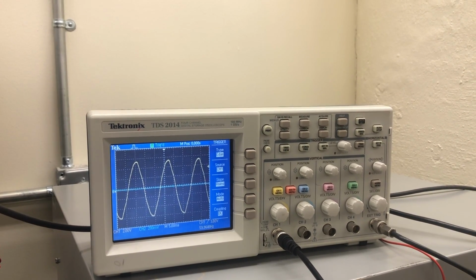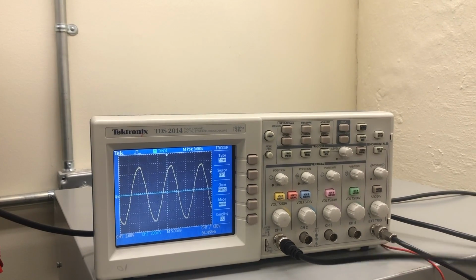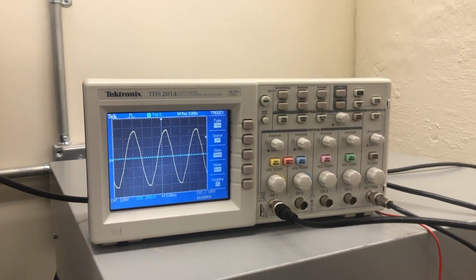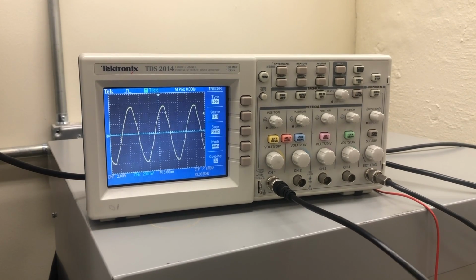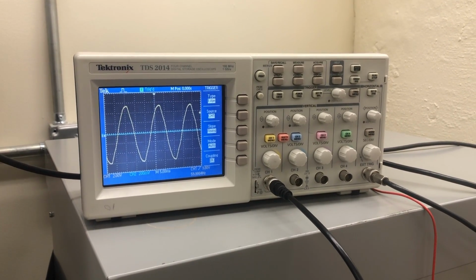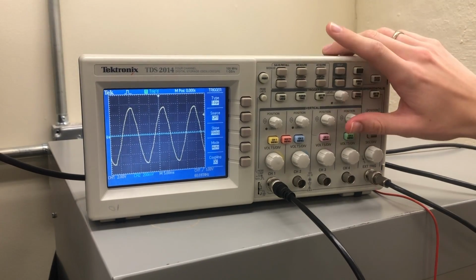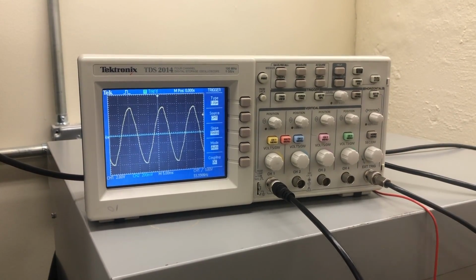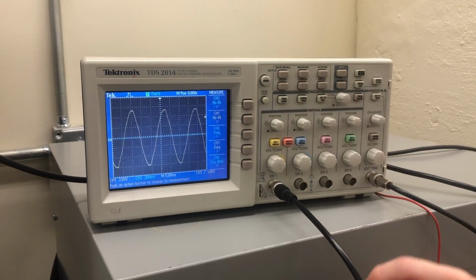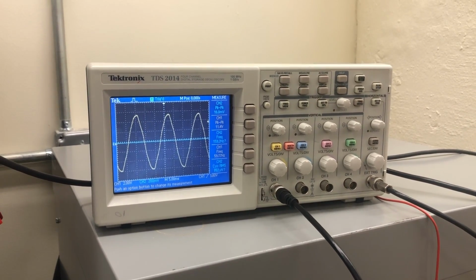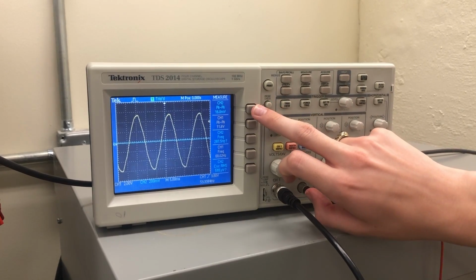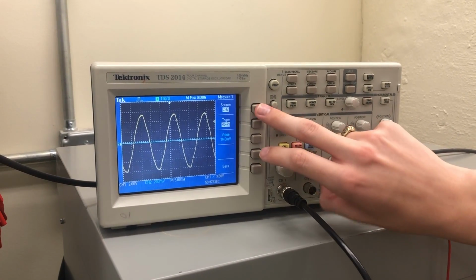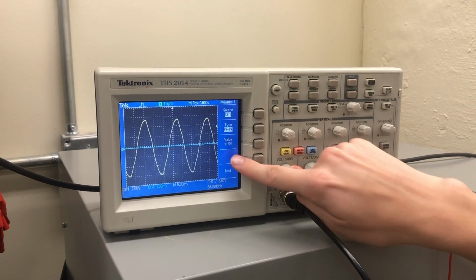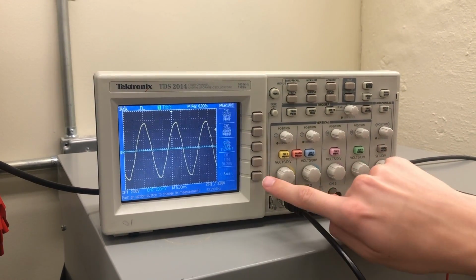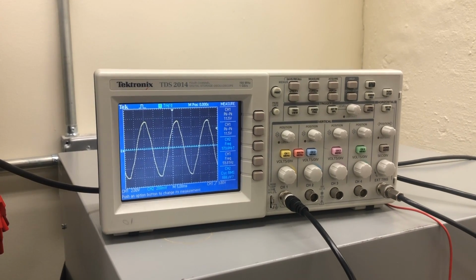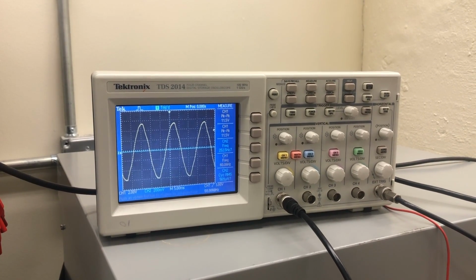This is one way to look at a voltage waveform, is to use the isolator built into your bench. There is another way that I'm going to demonstrate in one moment, but just for your information, if you want to set up some measurements on your scope, you're going to hit the measure button. Now you can set up different measurements for your channel. You change your source to channel 1. Peak-to-peak voltage is shown as 11.5 volts. Okay, so we know that's not the case. We know it's around 117 volts based on the measurement we took earlier.